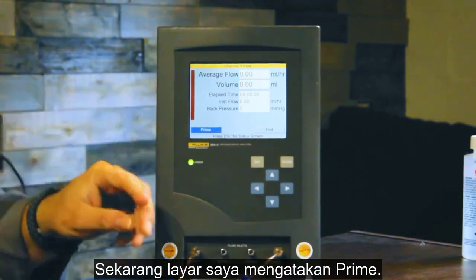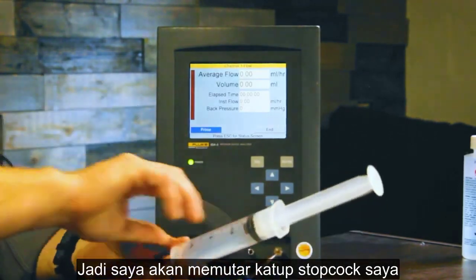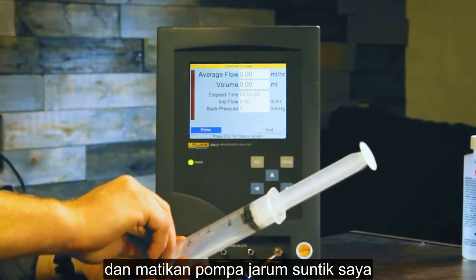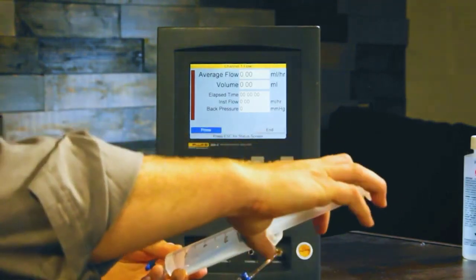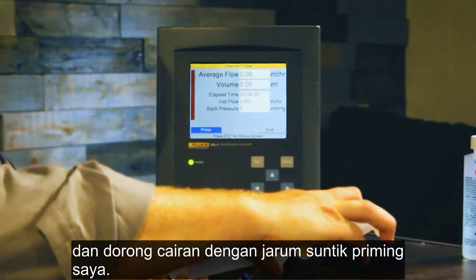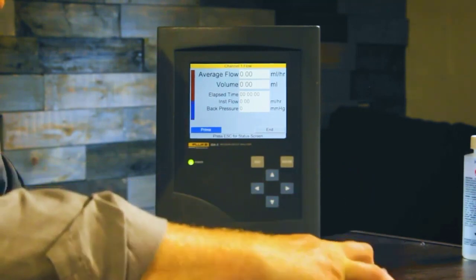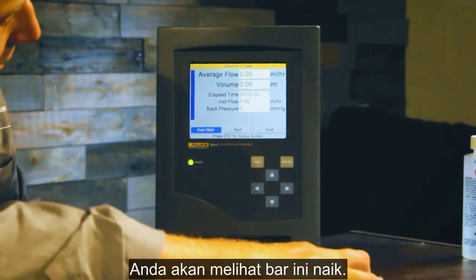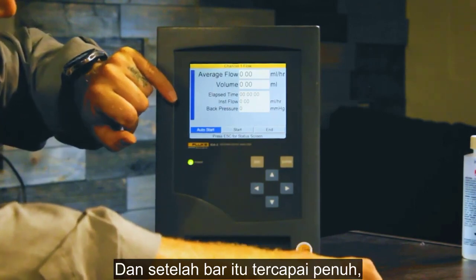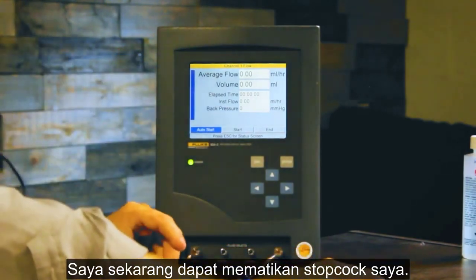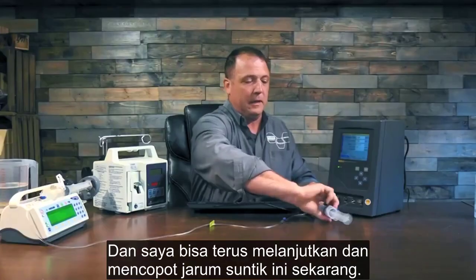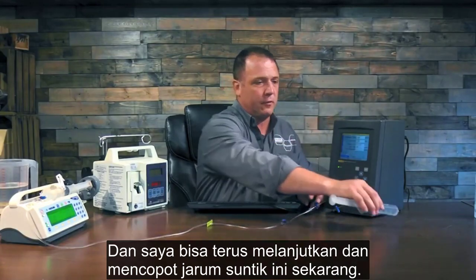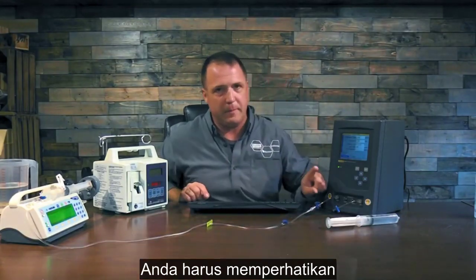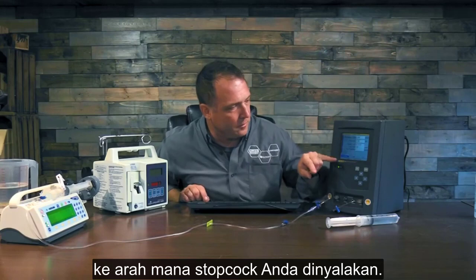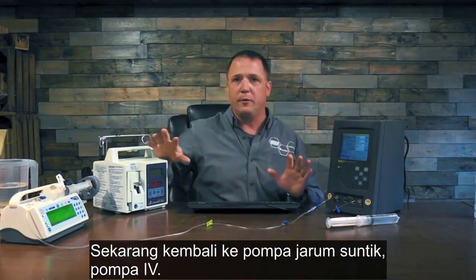Now my screen says prime, so I'm going to turn my stopcock and shut off my syringe pump and push fluid with my priming syringe. You'll see this bar go up, and once that bar is achieved, I can now shut my stopcock off, and I can go ahead and actually remove this syringe now. You've got to pay attention which direction your stopcocks are going. Now, back to syringe pumps, IV pumps.